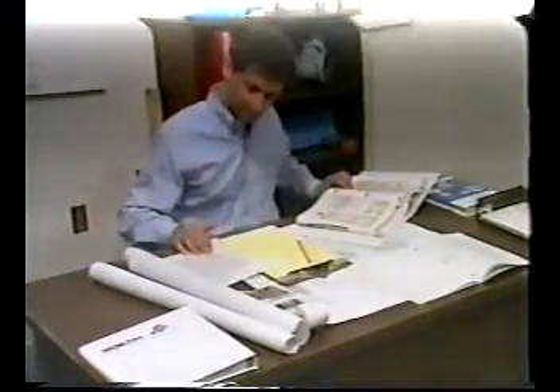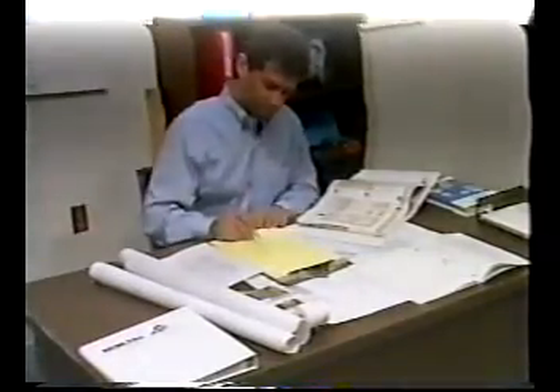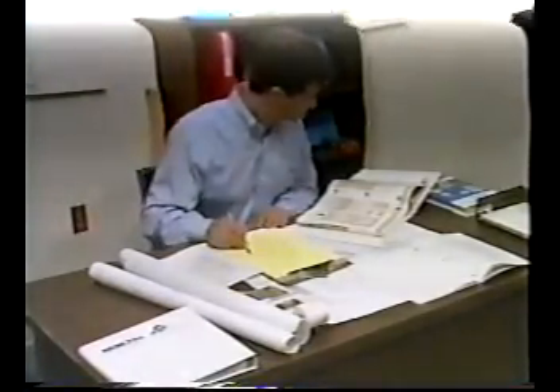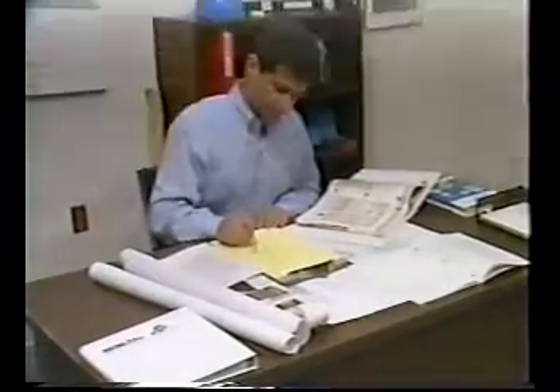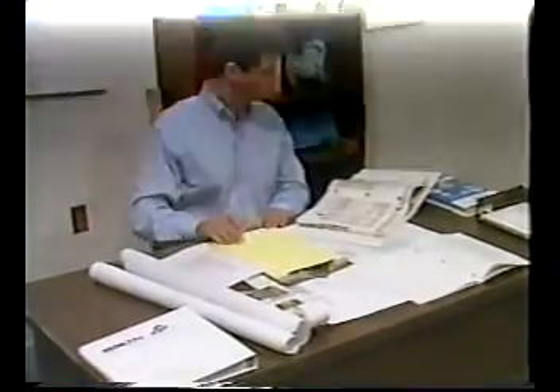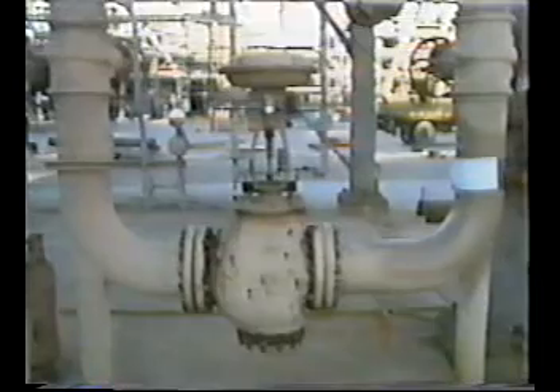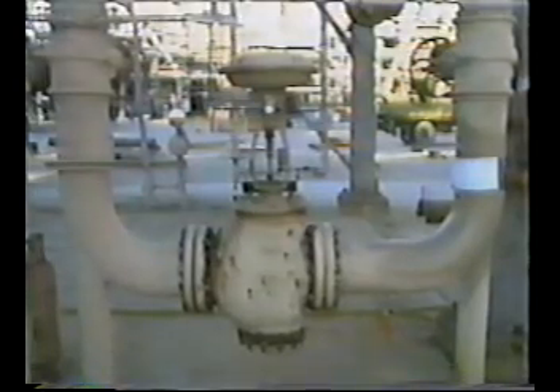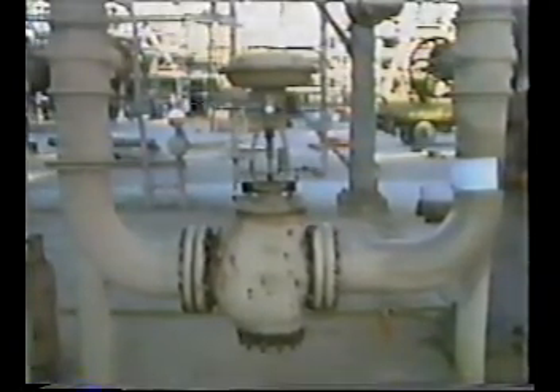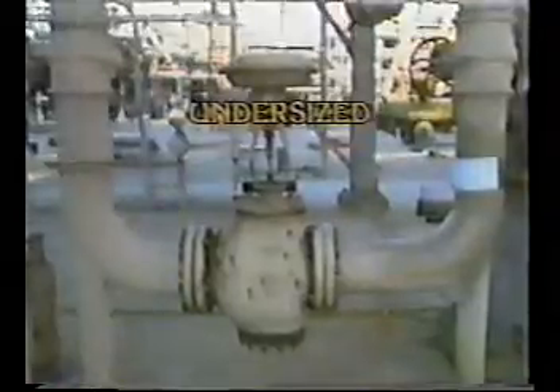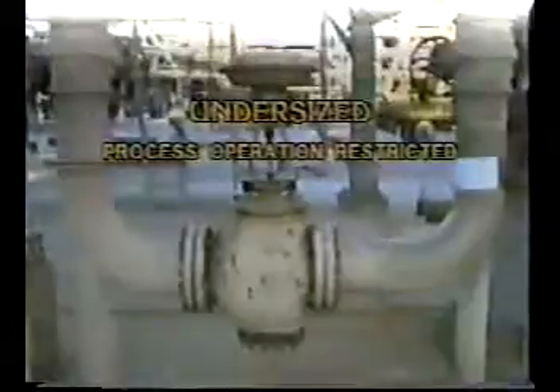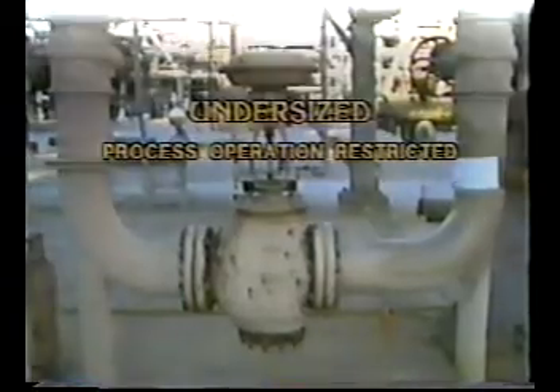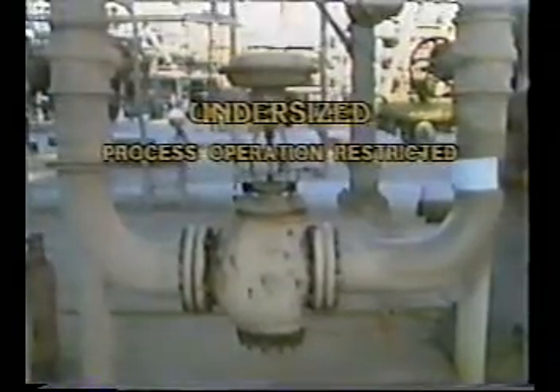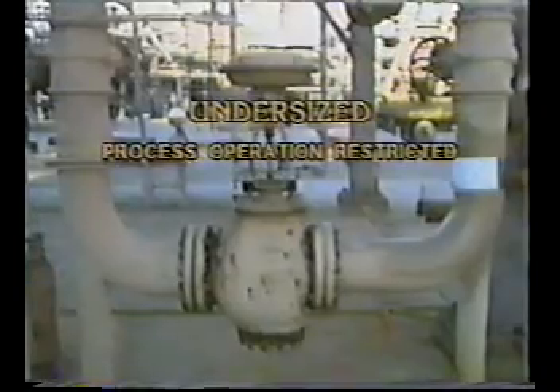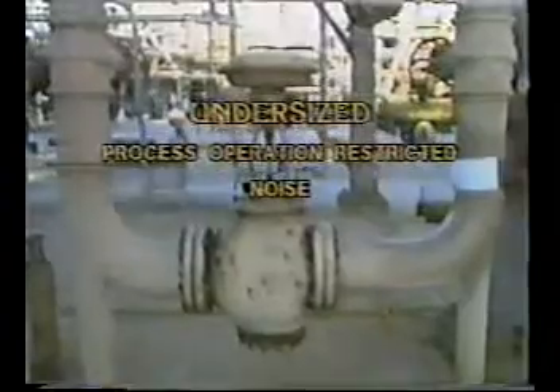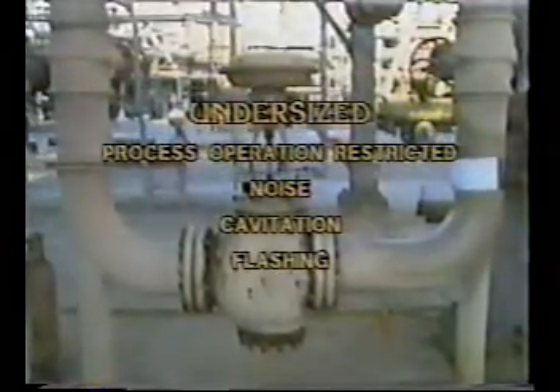After making a preliminary valve selection, it's necessary to determine the size of valve needed and to verify that the valve won't be subject to excessive cavitation or flashing. The importance of correctly sizing a control valve cannot be overstated. For example, if this valve were significantly undersized, process operation would be restricted to low flow rates only. And increasing differential pressure to obtain higher flow rates could result in excessive noise, cavitation, and flashing.